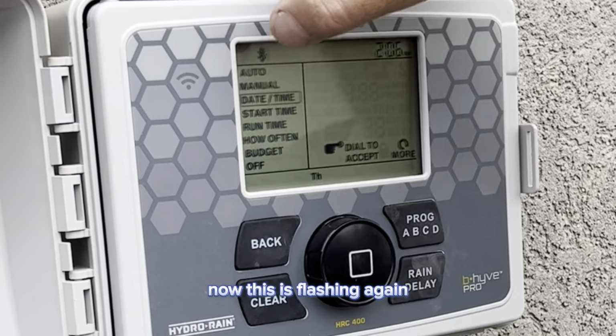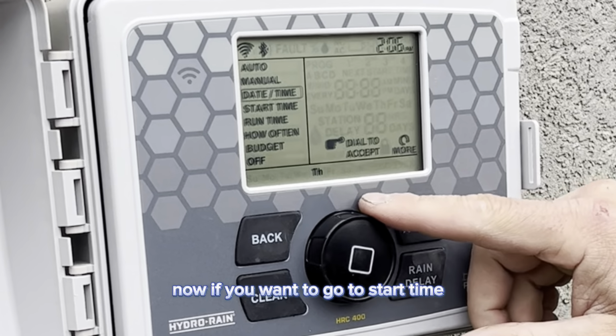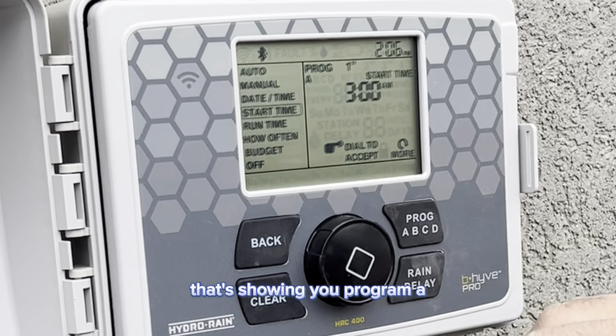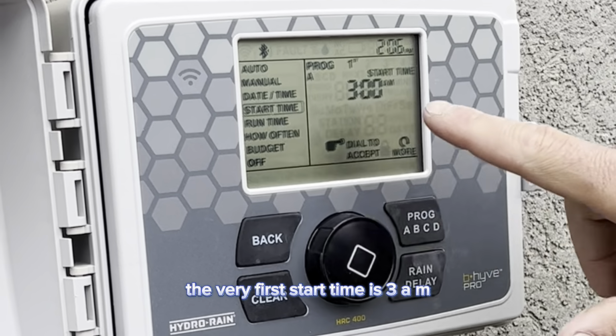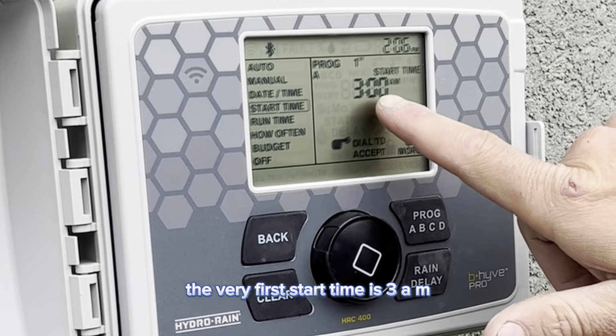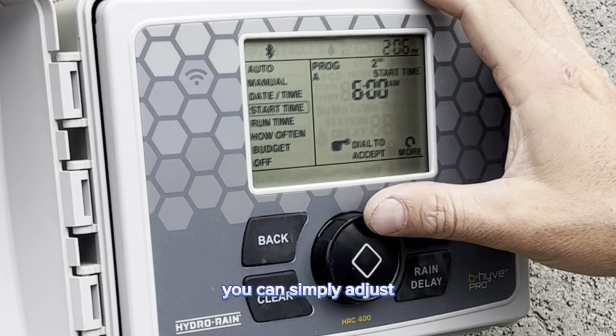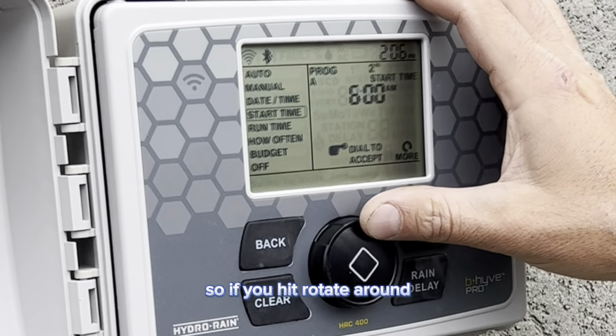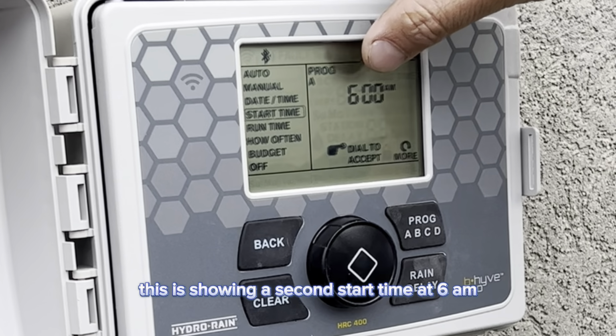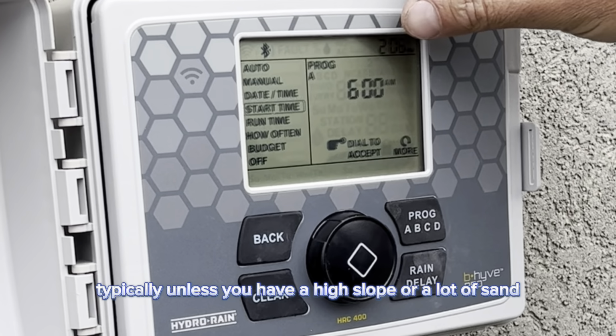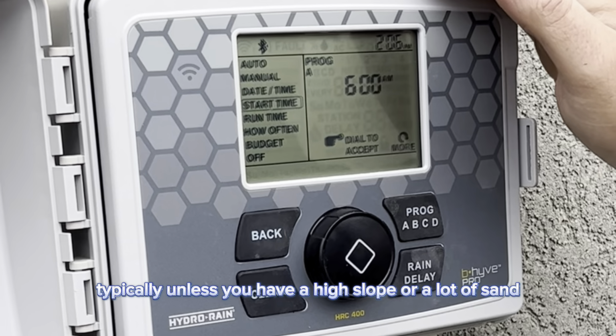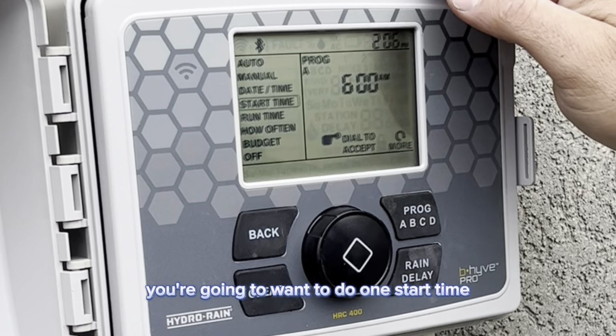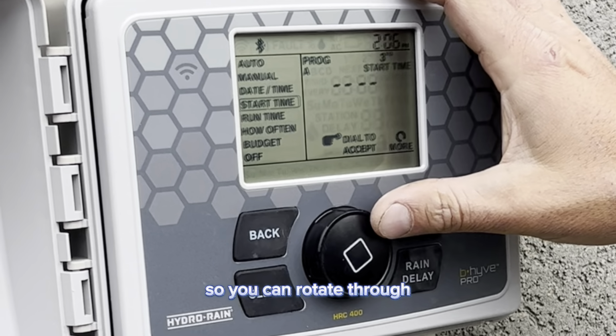Now this is flashing again, so you're back here. Now if you want to go to start time, that's showing you program A. The very first start time is 3 a.m. You can simply adjust. So if you rotate it around, this is showing a second start time of 6 a.m. We're going to want to change that. Typically, unless you have a high slope or a lot of sand, you're going to want to do one start time. So you can rotate through.